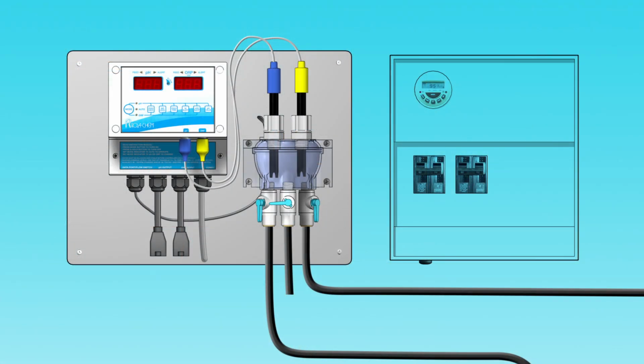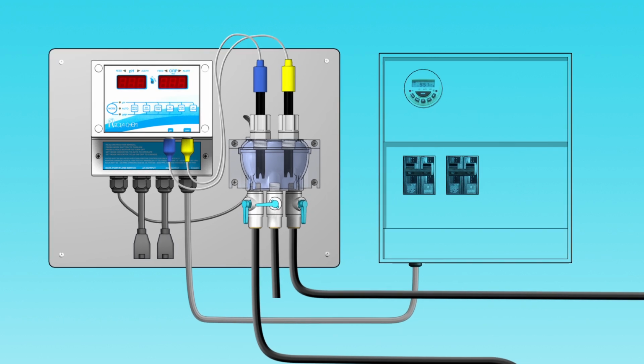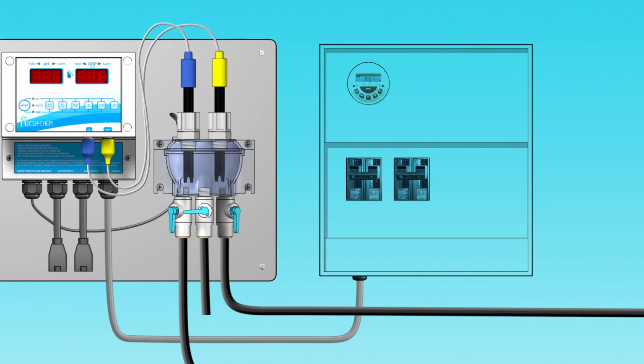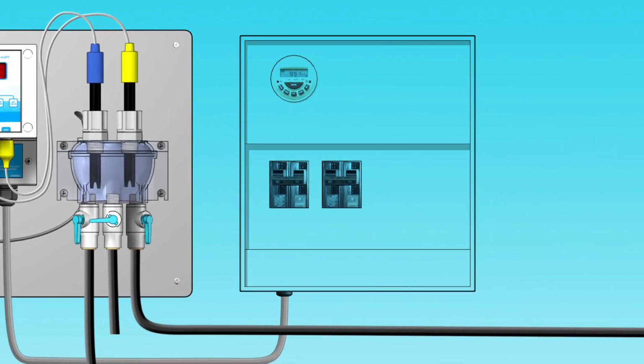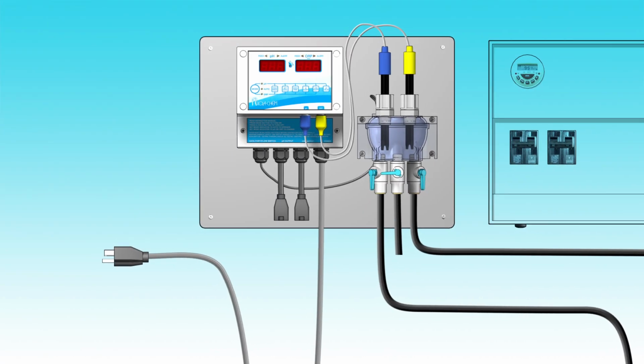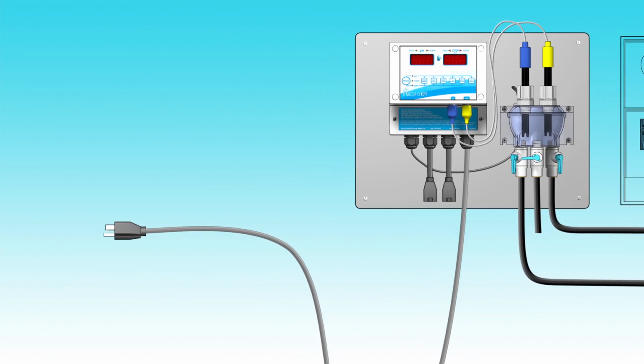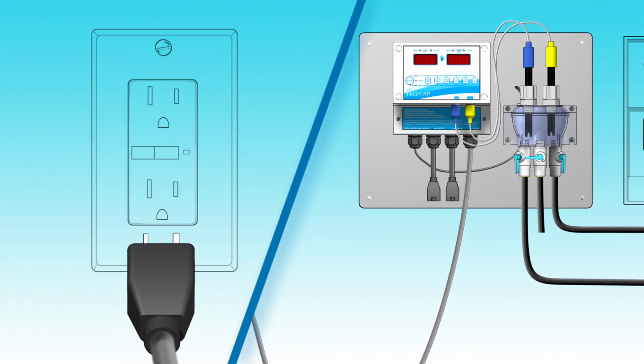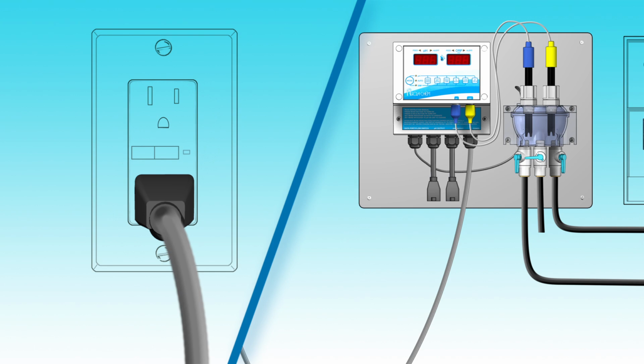To power the unit, have a qualified electrician wire the unit into the time clock on the load side of the circulation pump circuit. This will allow the unit to be turned on only when the system turns on. As an alternative, you may also plug the 3-pronged grounded plug into a GFCI outlet powered by the circulation pump circuit.